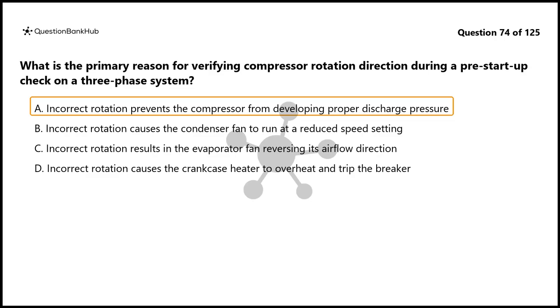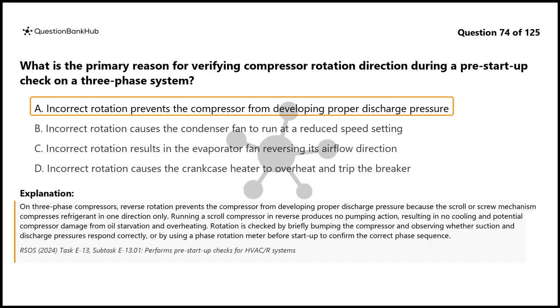The correct answer is A. On three-phase compressors, reverse rotation prevents the compressor from developing proper discharge pressure because the scroll or screw mechanism compresses refrigerant in one direction only. Running a scroll compressor in reverse produces no pumping action, resulting in no cooling and potential compressor damage from oil starvation and overheating. Rotation is checked by briefly bumping the compressor and observing whether suction and discharge pressures respond correctly, or by using a phase rotation meter before startup to confirm the correct phase sequence.